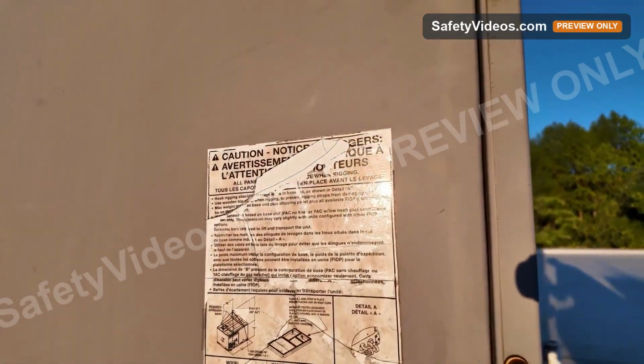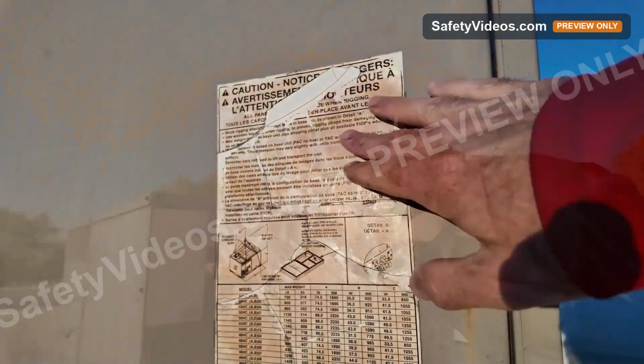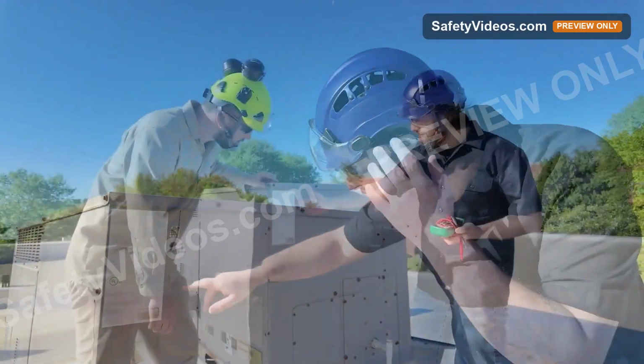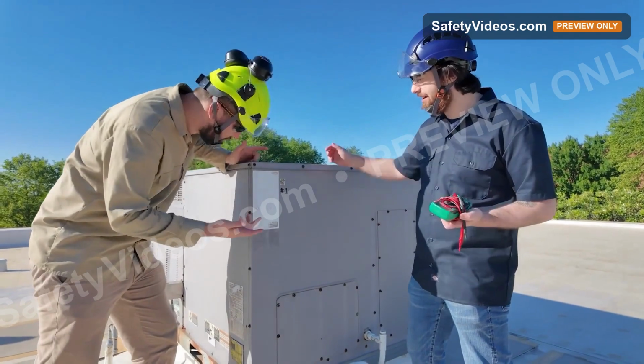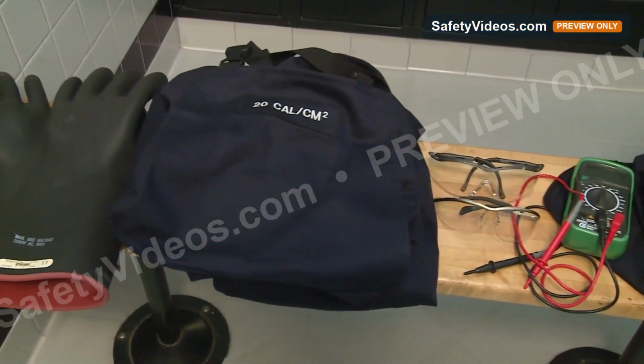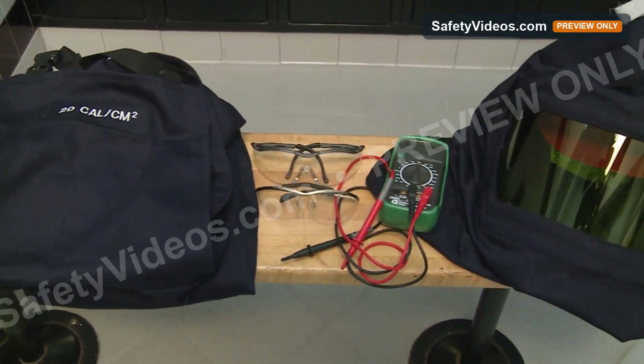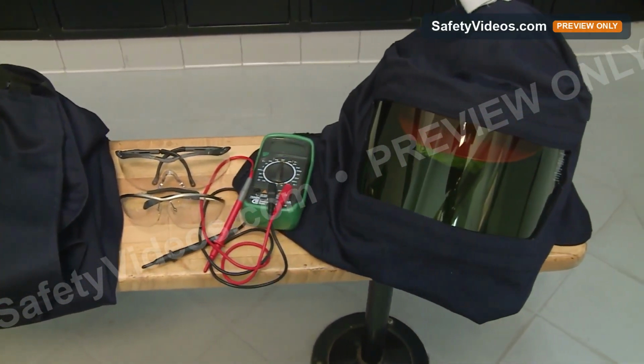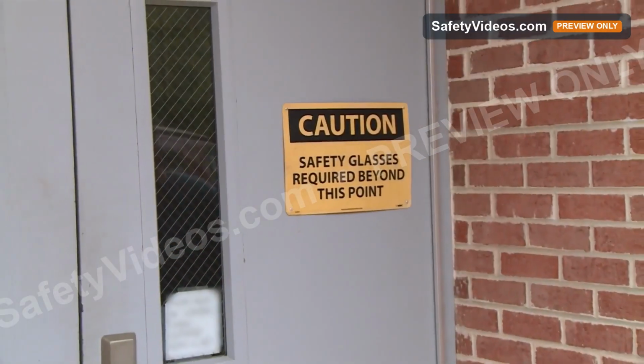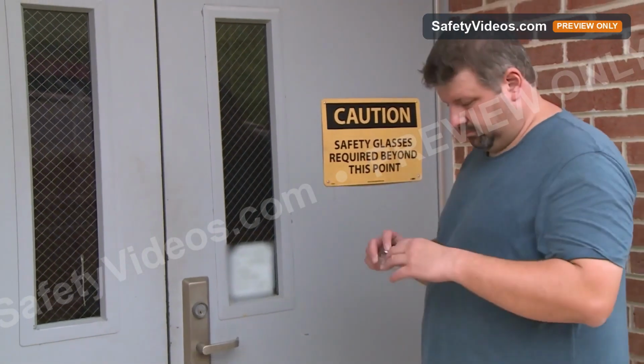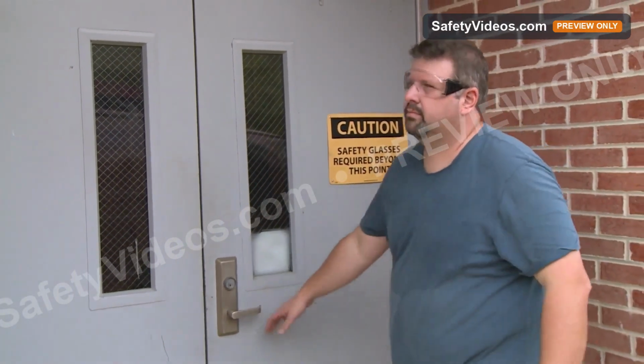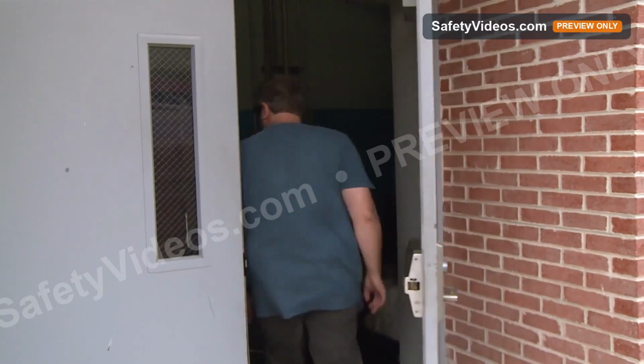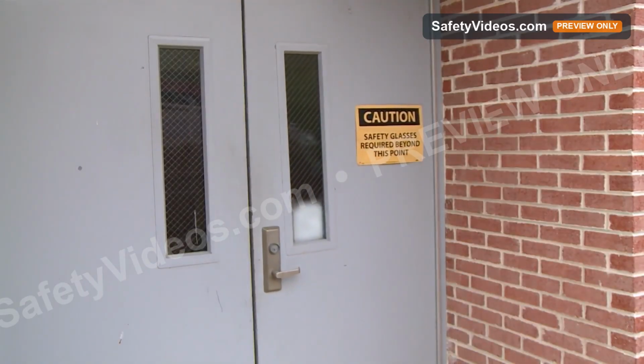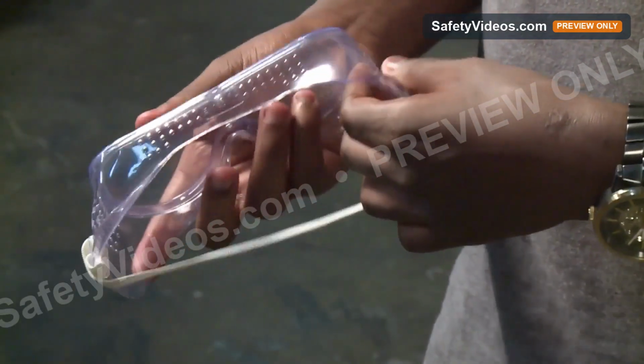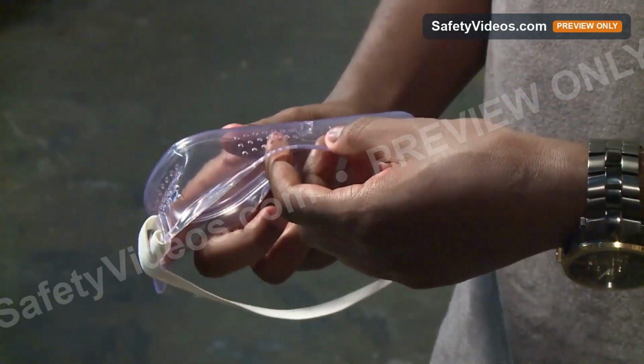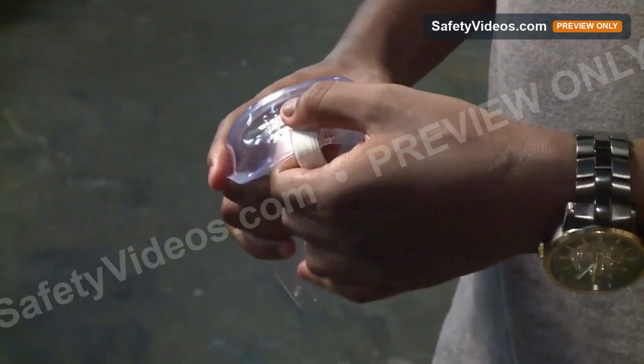If a label isn't durable enough to withstand the environment it's in, or you have trouble reading it, notify your supervisor. Another thing that NFPA 70E discusses is the use of personal protective equipment, PPE. Remember, PPE is the last line of defense. Without other protection measures, it can't protect you from all of the potential injuries that could occur on its own. However, it can minimize the severity of injuries, as long as it is maintained in a safe, clean, and reliable condition.